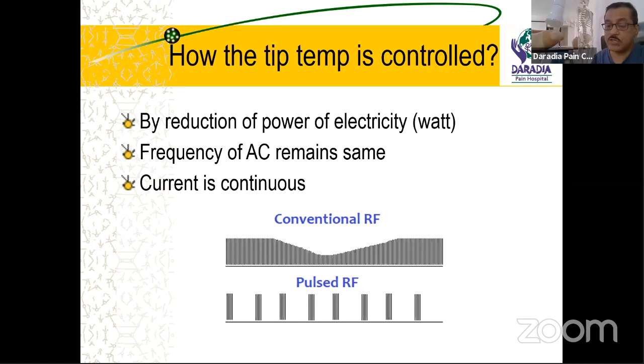So now a little bit more details about the pulse radio frequency. What is done here? We are delivering packets of the alternating current in between with the silence. Two important things to remember. One is, what is the duration of this active current? How long are we giving this active current, and how frequently are we giving it, or what is the gap between two active currents? That is what determines the pulse radio frequency parameters. So remember, most machines have this parameter, 2 hertz, 20 millisecond pulse radio frequency.